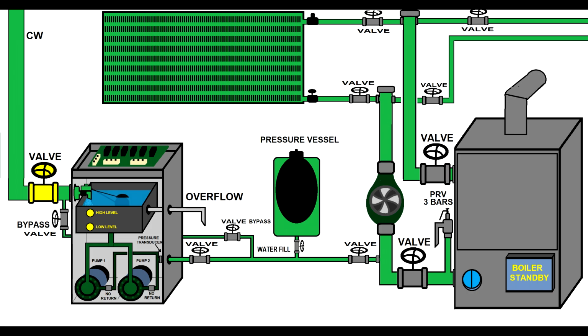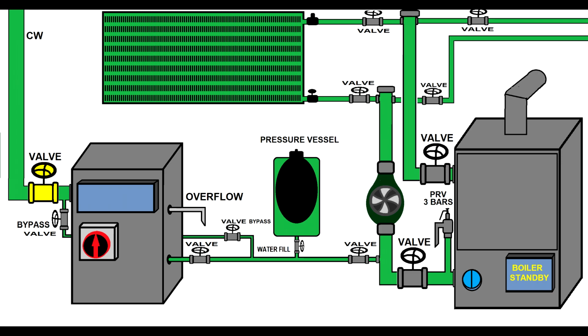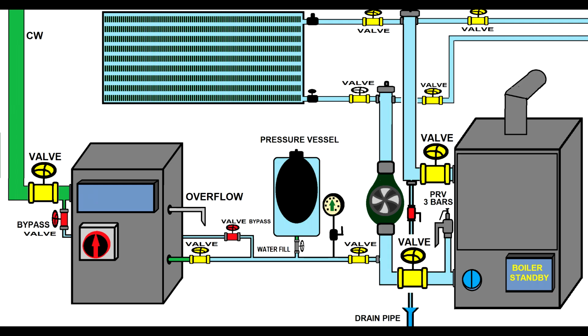While the tank is filling up, we have a good chance to observe if we have any water leaks. Now we made sure we don't have leaks, the pressurization unit tank is filling up, everything is okay, we can put the lid back. After we sorted out the pressurization unit, it is time to open all the relevant valves on the heating system.